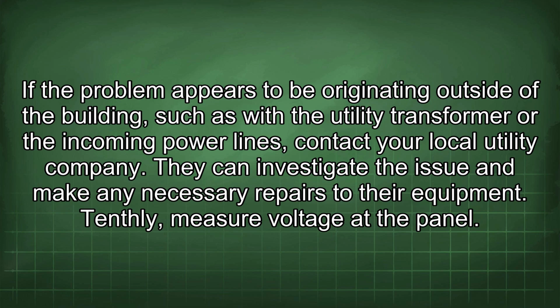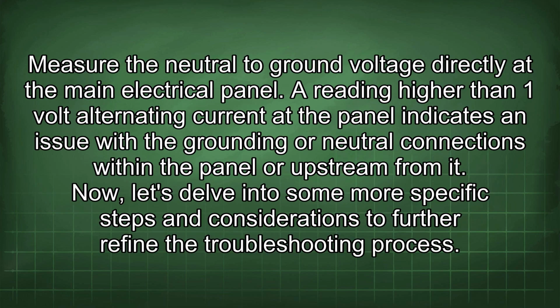Tenthly, measure voltage at the panel. Measure the neutral to ground voltage directly at the main electrical panel. A reading higher than 1 volt alternating current at the panel indicates an issue with the grounding or neutral connections within the panel or upstream from it.